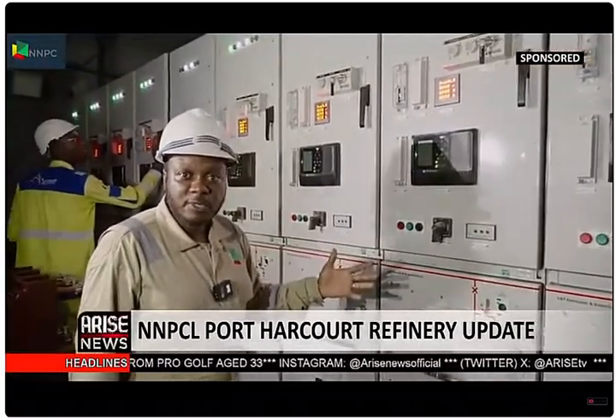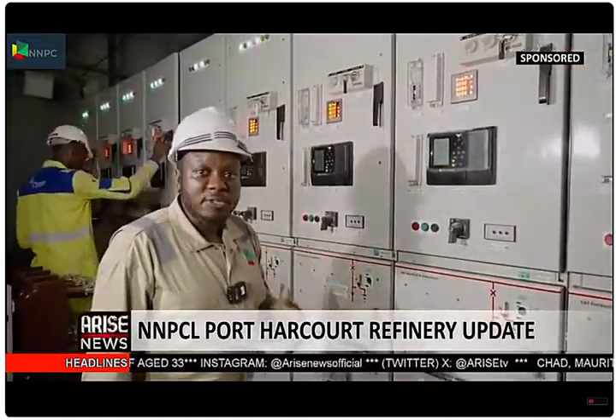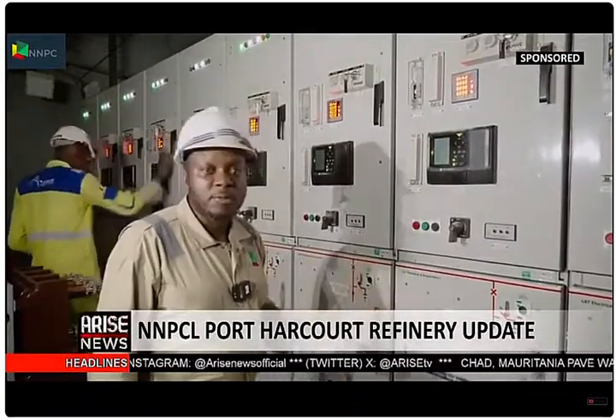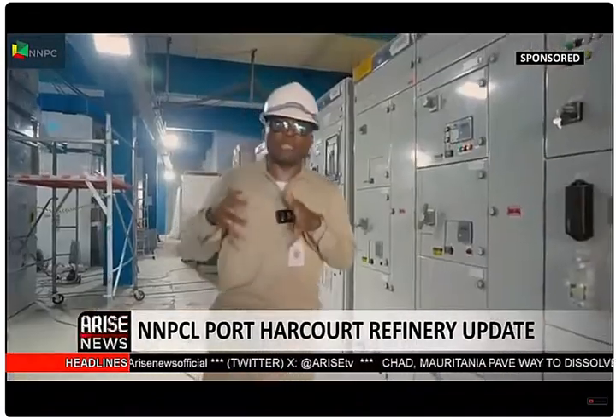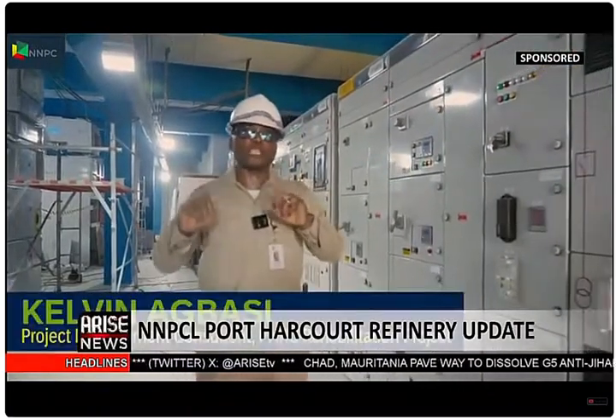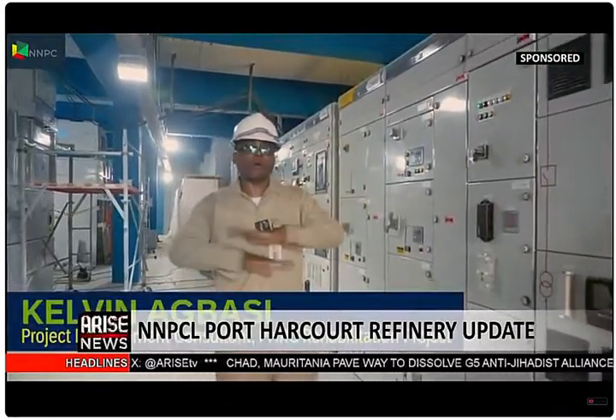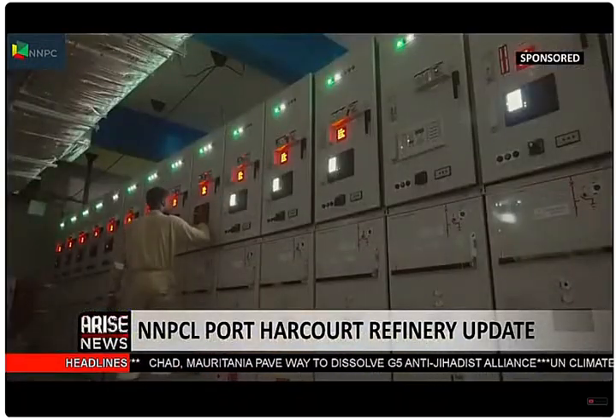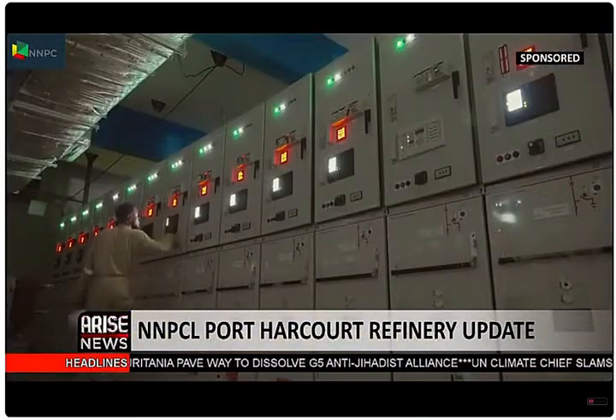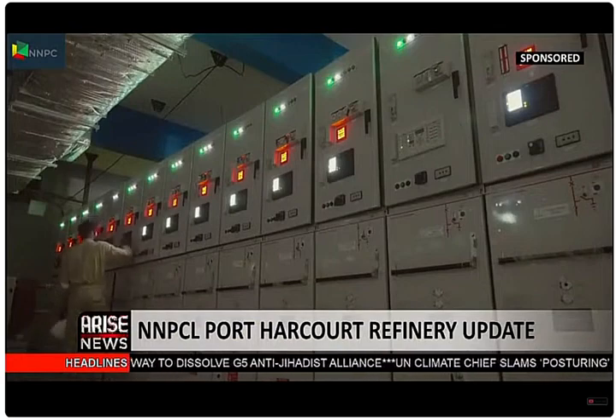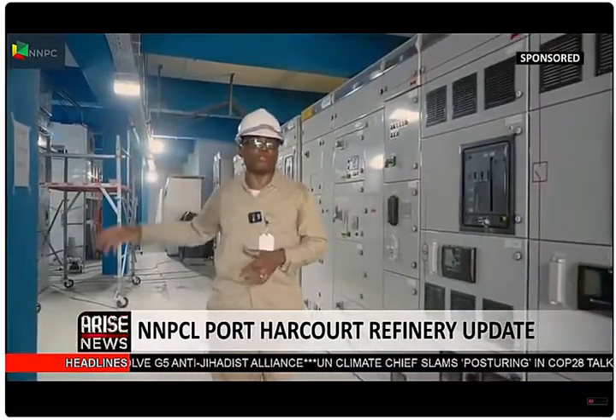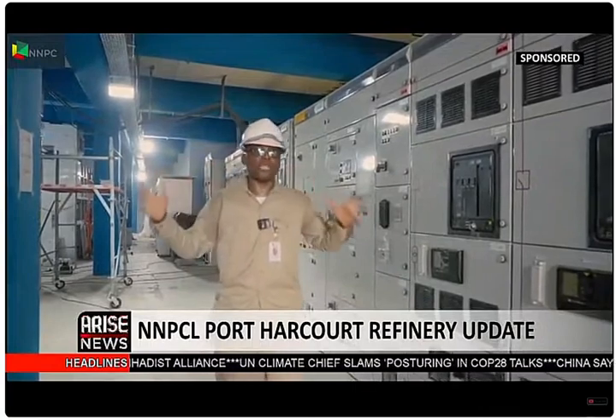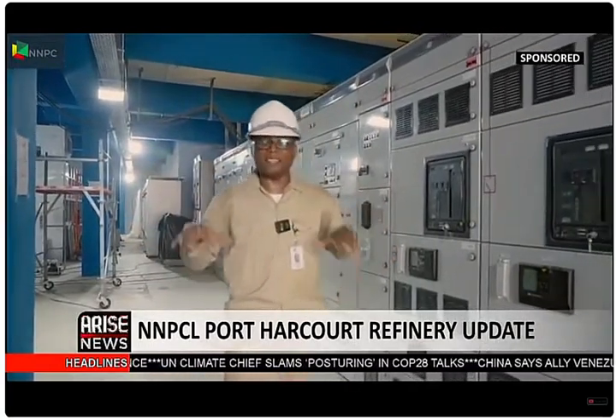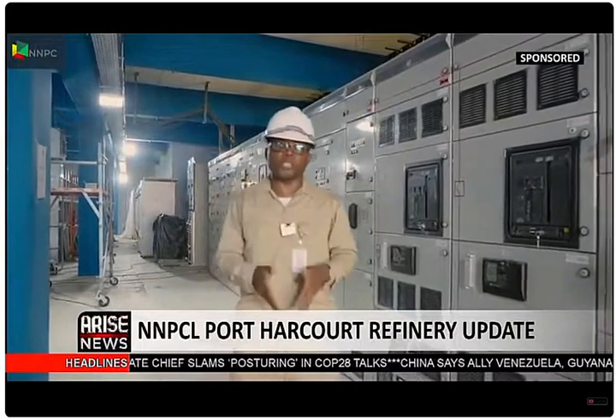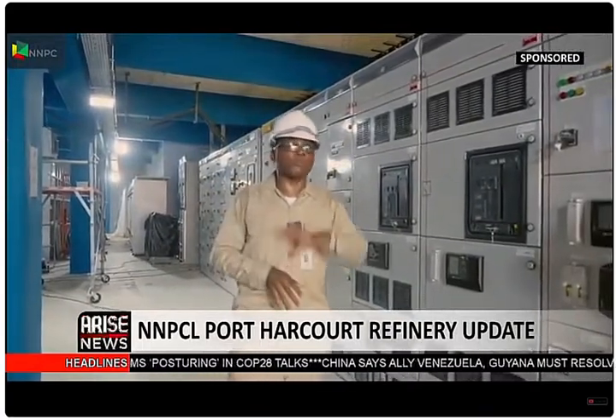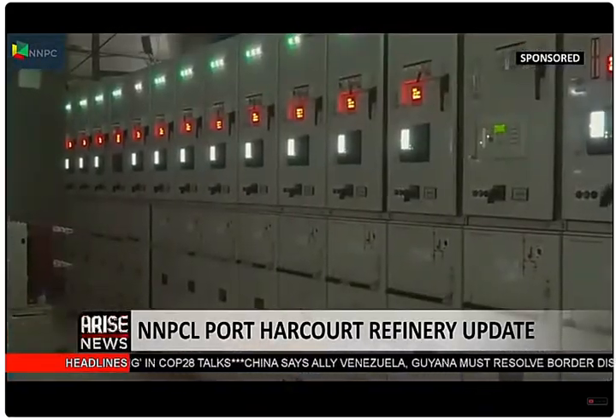Commissioning is ready for sub 1. Sub 1 is commissioned, and we are just doing the final check so that we can send out power to the other substations. Then immediately from sub 1, it is transmitted to the substation B, which powers all area 5 substations. And also from here, we power the PPU, we power the life camp, we power the wastewater, and we power the new refinery. So it all indeed starts here. This is the primary substation for the Port Harcourt refinery, both old and new.